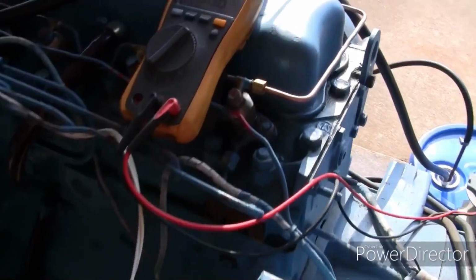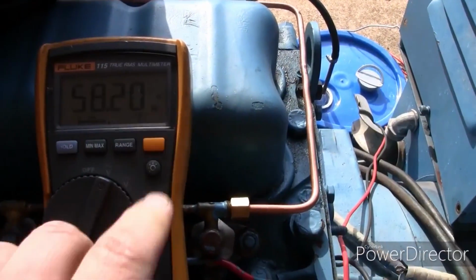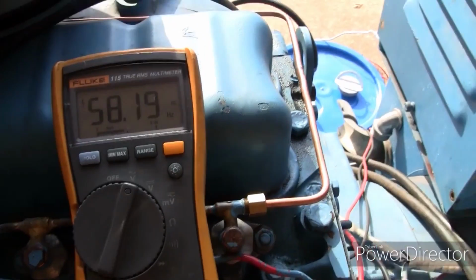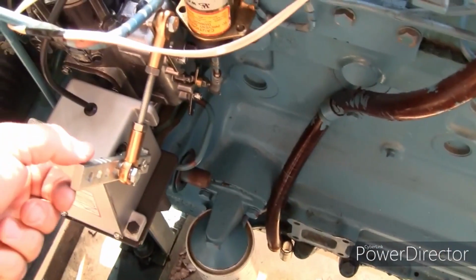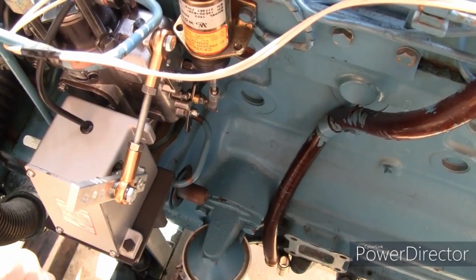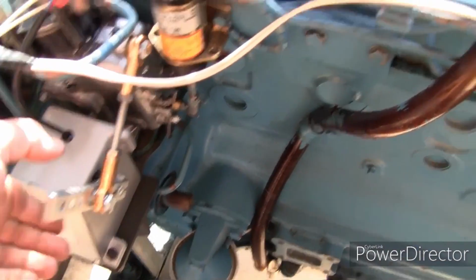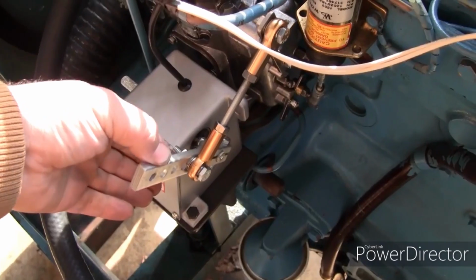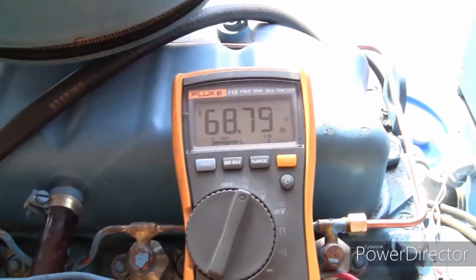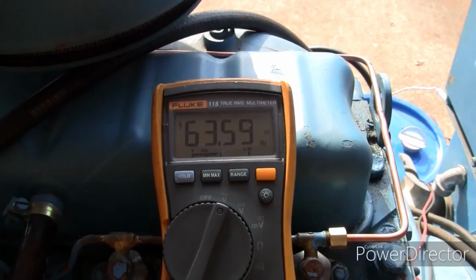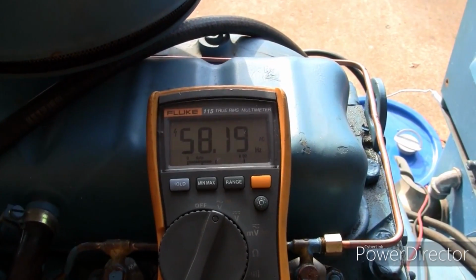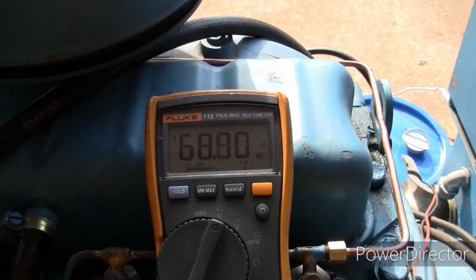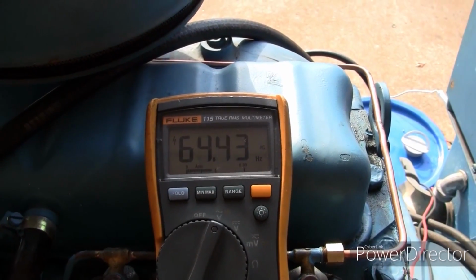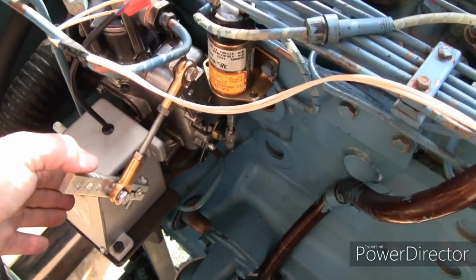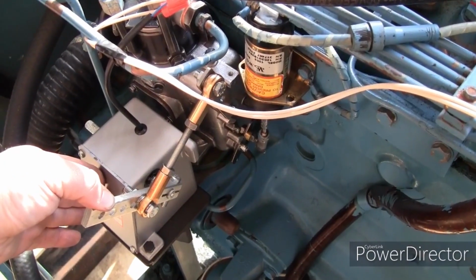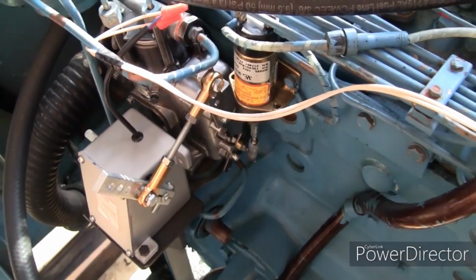So right now we've got the engine running. It's at about 58 hertz, 58.2. That's with the governor essentially doing nothing. So you can see I'm revving the engine a little bit here. Got full throttle, we're at 68 hertz. Minimum throttle 58. So we've got 10 hertz worth of adjustment with the governor actuator. That's its maximum amount of adjustment that it can provide to the engine under no load conditions.